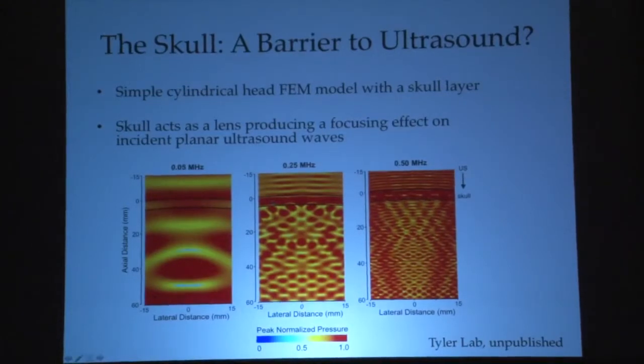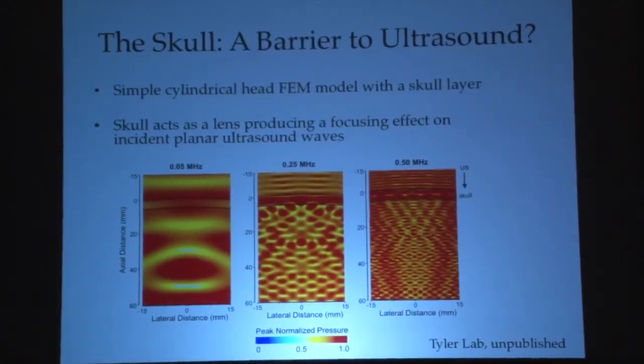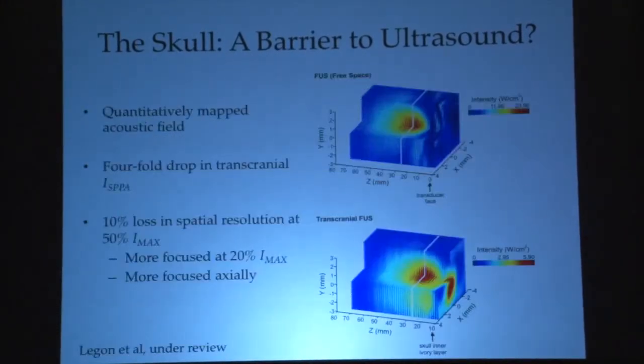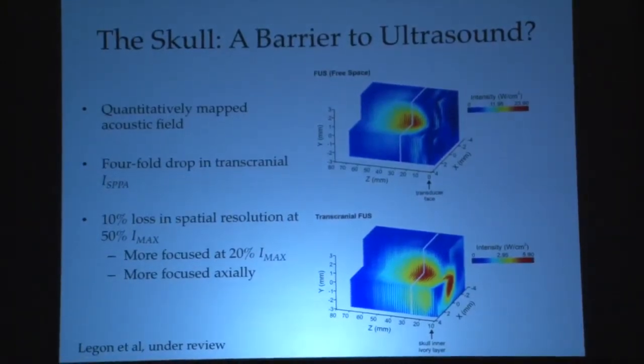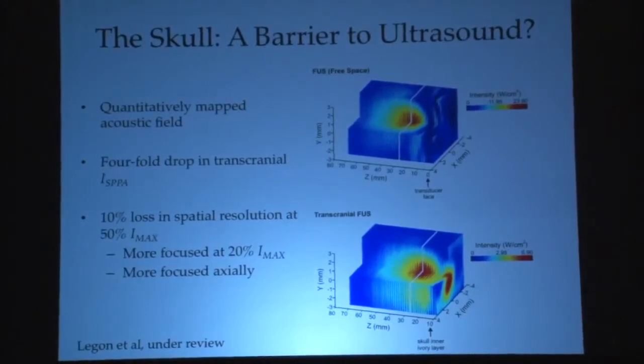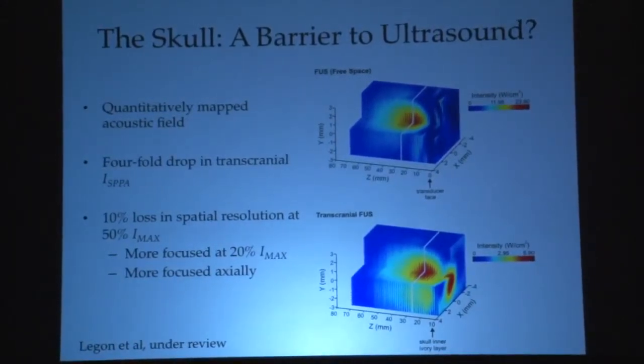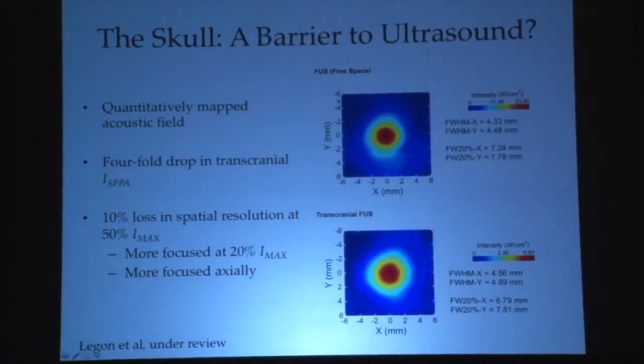What we found when we put these models to a test and quantitatively mapped acoustic fields using customized single element focused ultrasound transducers is that the skull actually acts as a lens to ultrasound. It actually focuses the ultrasound slightly, mostly in the axial direction, not so much in the lateral direction. And here you can see the acoustic field maps obtained in free space as well as through hydrated fragments of human cranium. You can also see here, this is basically the beam profile, the lateral beam profile.